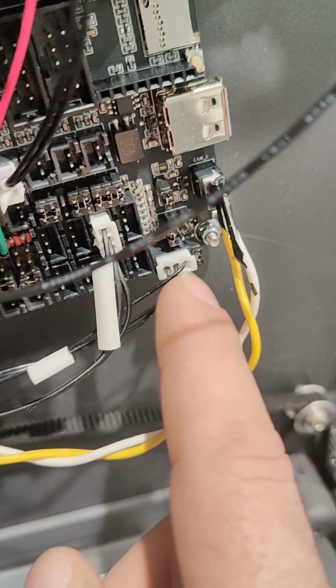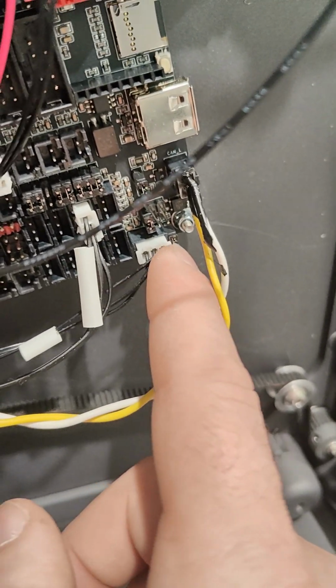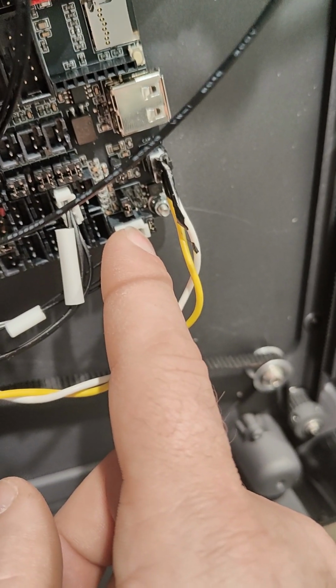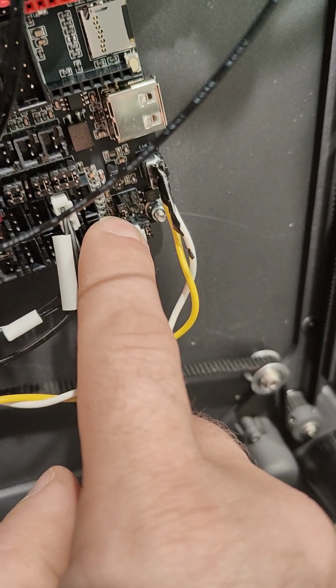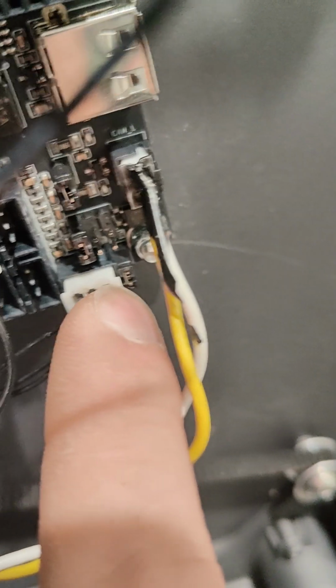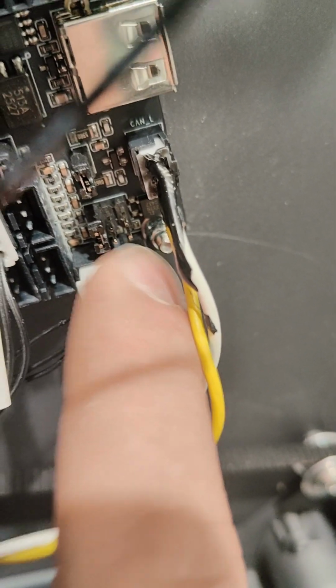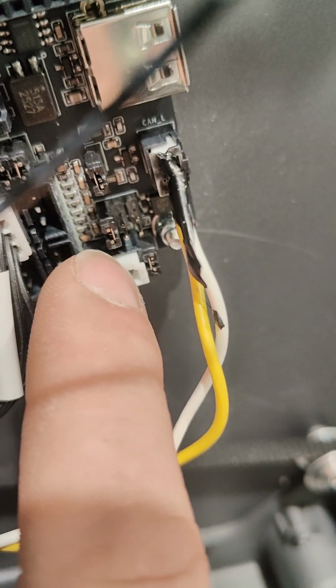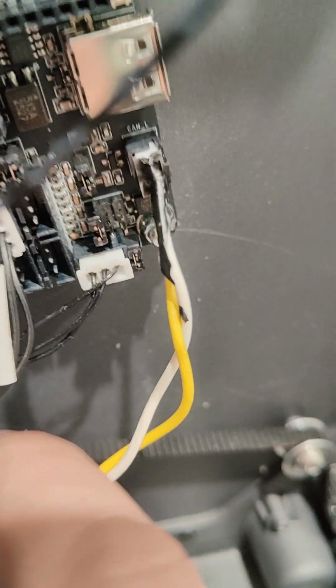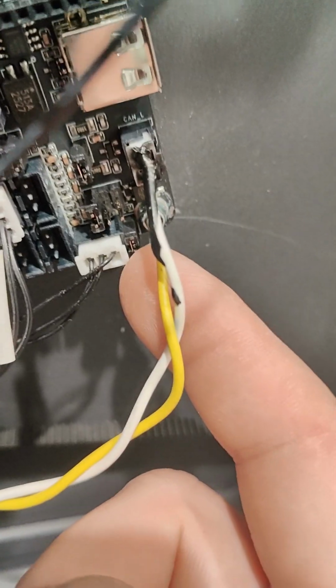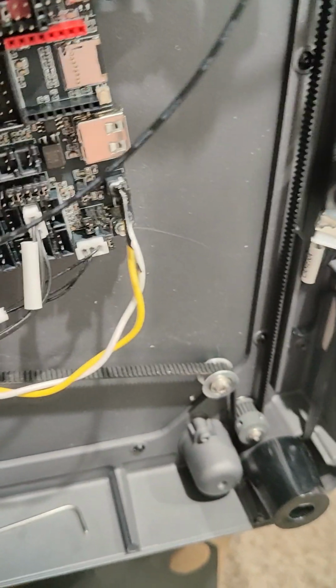This is your probe one, like I was saying. You have to change the two outside wires. This probe runs off of 24 volts, so you just move this pin to this slot. You see there's 3 slots: the first slot's 5 volts, 12 volts, and then the last slot is 24 volts. And then you want this resistor in here too, because that does a pull up, I believe, for the sensor, and you need that.